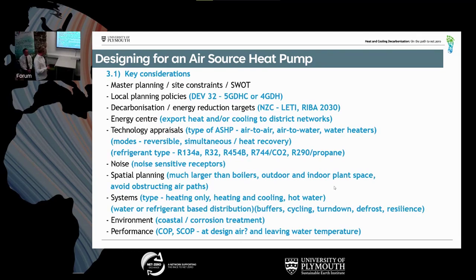Systems - this is kind of linked to the other modes of operation, but you can have heating and cooling, heating only, and you can have hot water. The important decision, I suppose, from a design perspective is, do you want to have a water-based distribution system or a refrigerant-based distribution system? And really what informs that is efficiency. It's more efficient with refrigerant distribution, but you need AC specialist installers and maintainers. Whereas with a water-based system, it's for plumbers and it's less specialist. So that's something to consider.